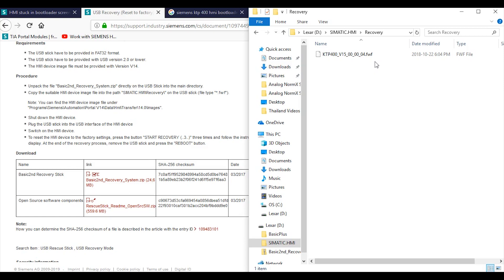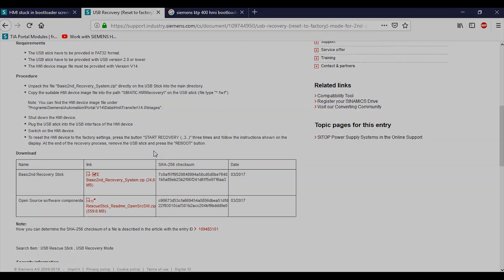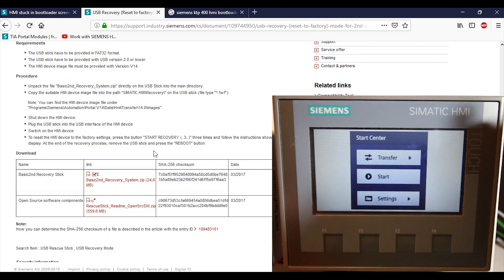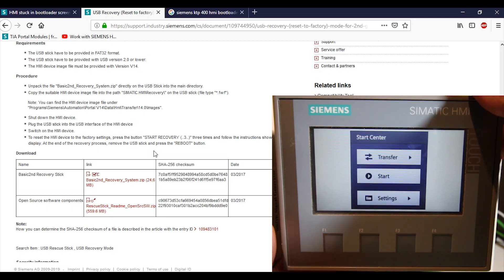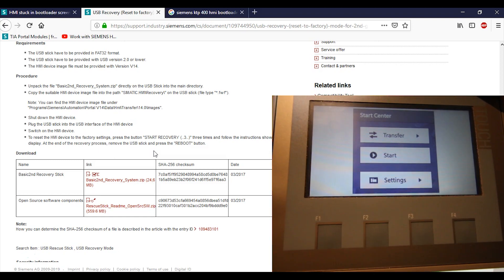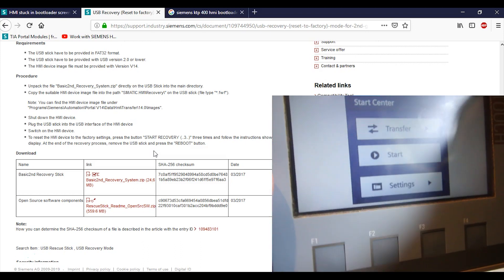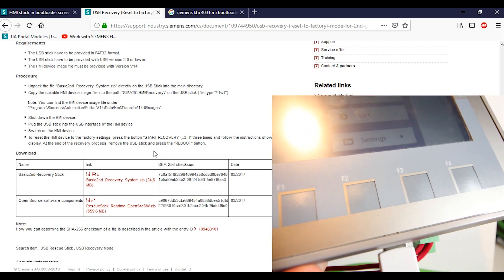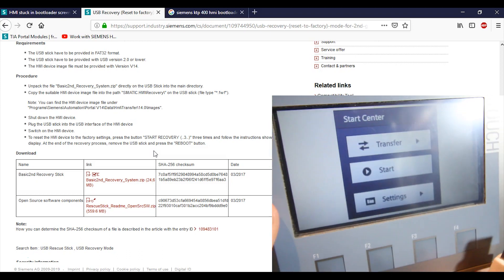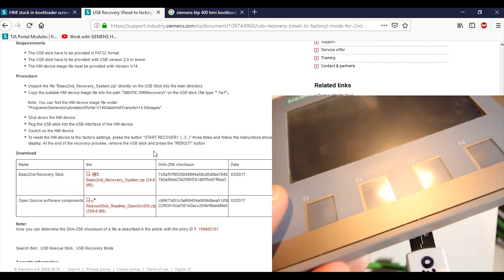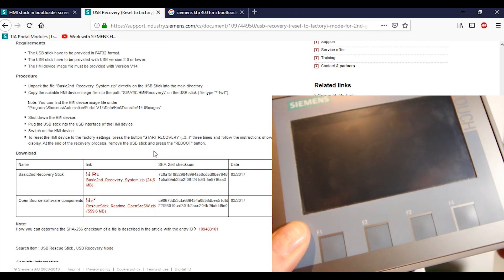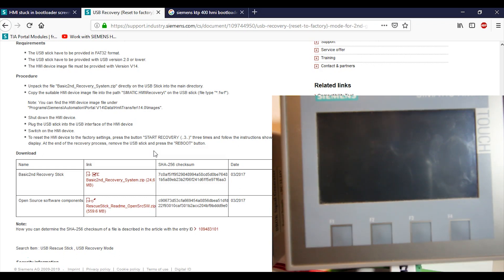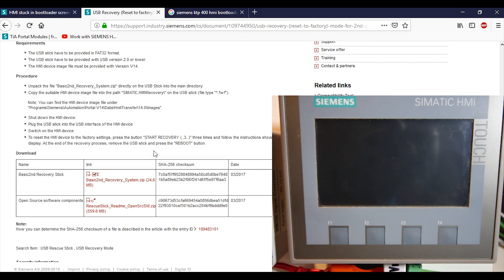I can't have my laptop talk to my HMI, but I can sure enough put a USB stick into there and then reset the HMI and have it boot from this stick. It says to shut down the HMI device, plug the USB stick into the USB interface of the HMI, switch on the HMI device, and to reset the HMI to the factory settings, press the button Start Recovery three times. So we're going to take out the USB and we're going to put this guy into the bottom of our HMI. I'm going to take my ethernet cable out, I'm going to shove the USB stick in, but first I have to turn off my HMI. Let me just stick it right back on there. Something's in the way - oh, the USB stick's in the way. Beautiful.